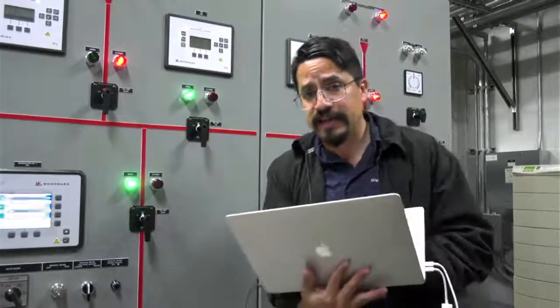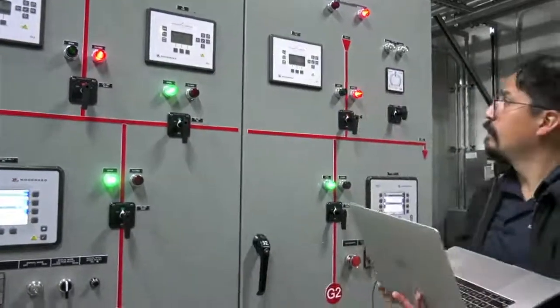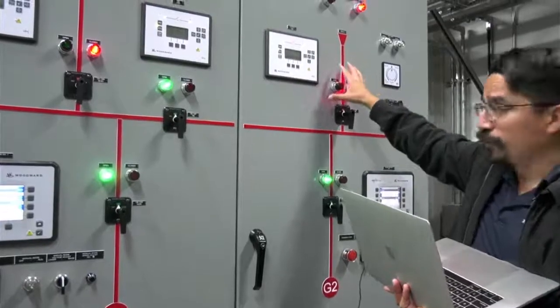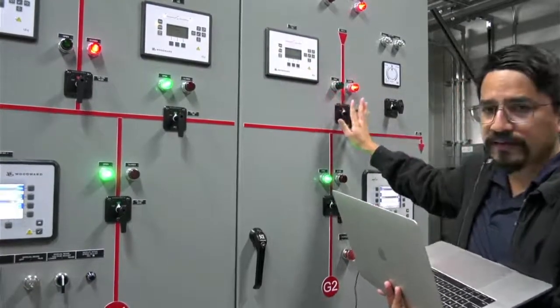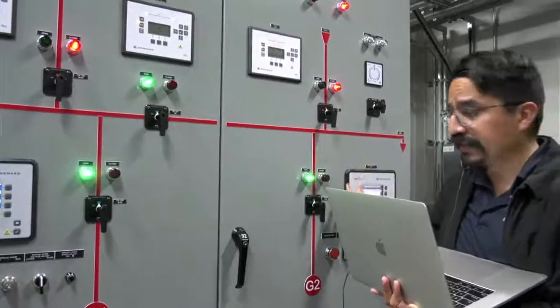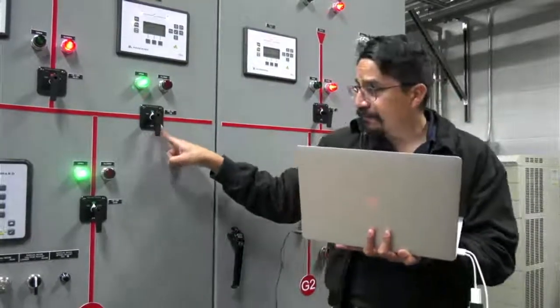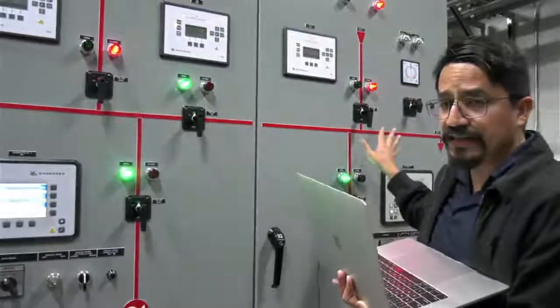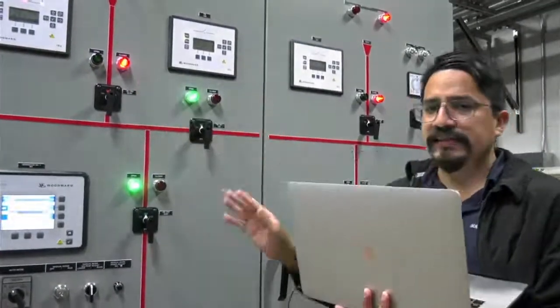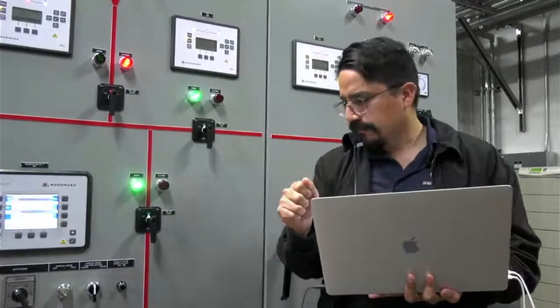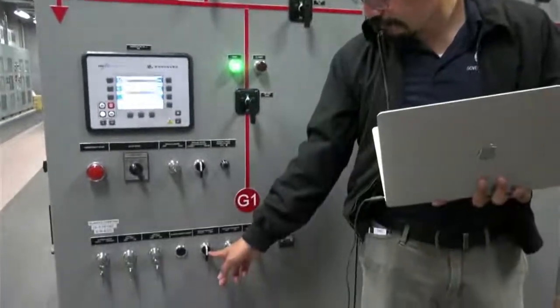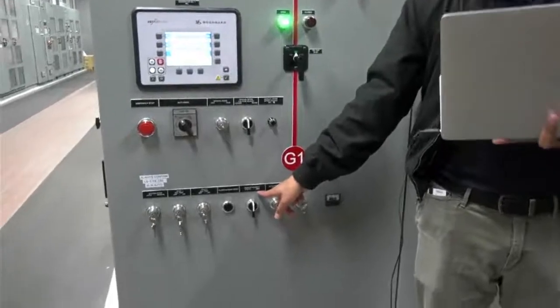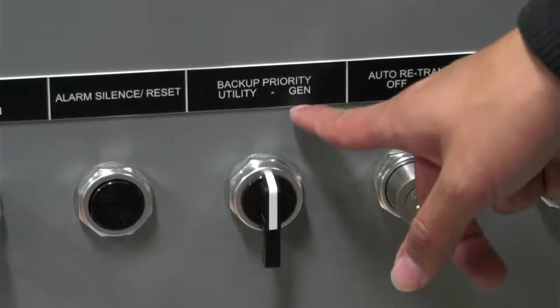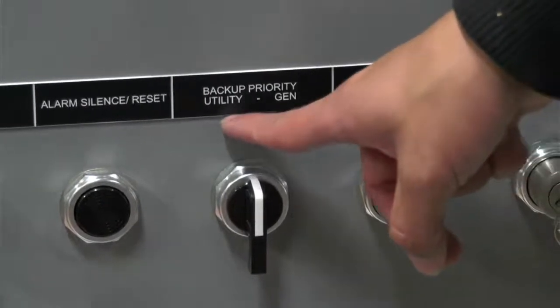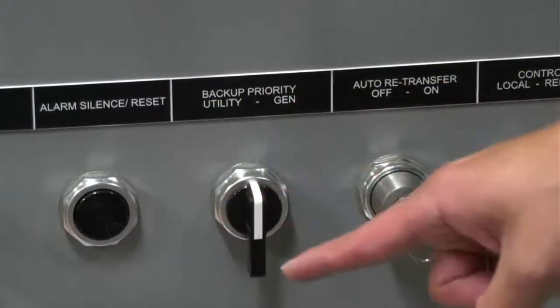The priority on the utility means that if you lose Tico 2, after a delay time it's going to open this circuit breaker. It's not going to run the generator, but it's going to close the tiebreaker instead, energizing this side of the bus with Tico 1. So that's the main difference of the priority. You can change the priority over here. So with priority on generator, if one side fails, it's going to run the generator and energize that side with the generator. And if the priority is on utility, the tiebreaker will close and it's going to energize using the remaining Tico.